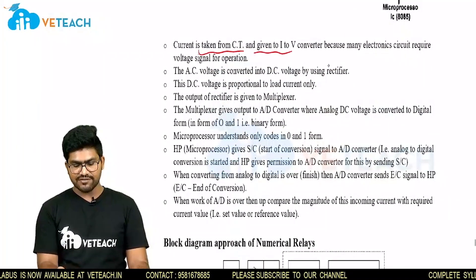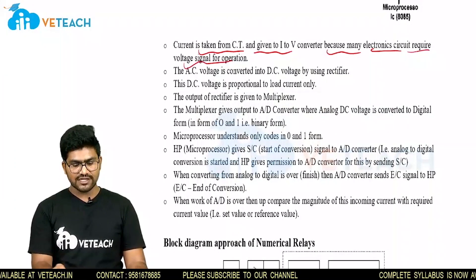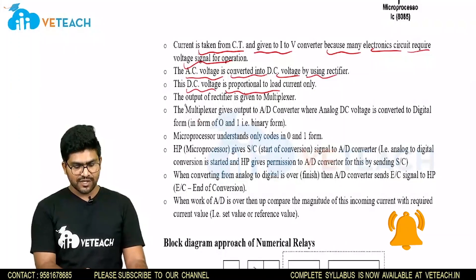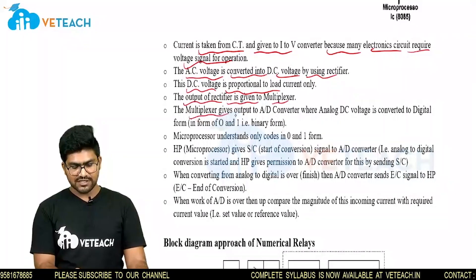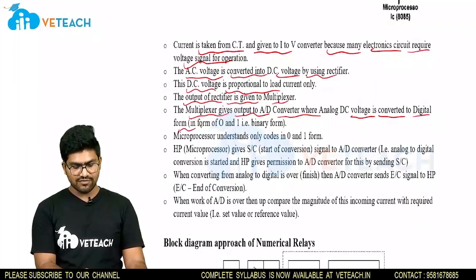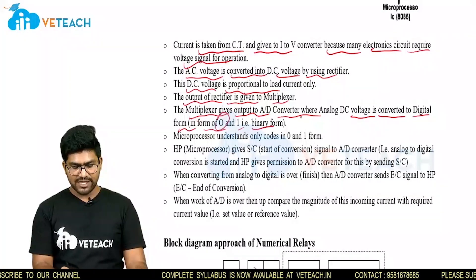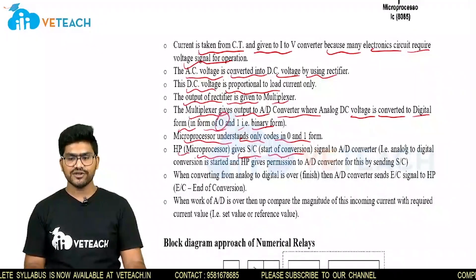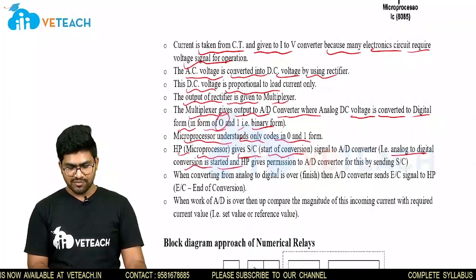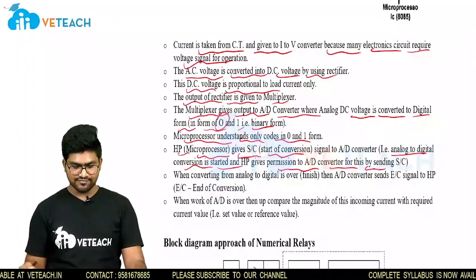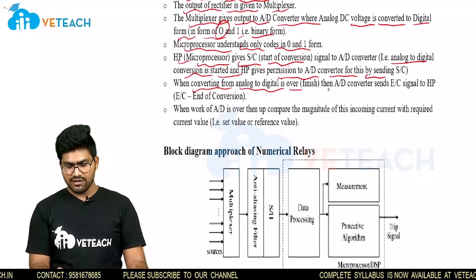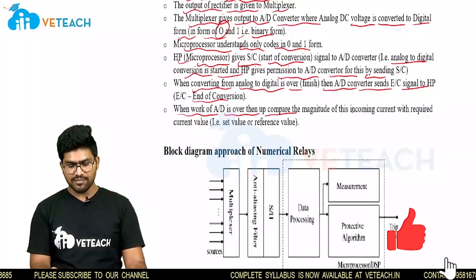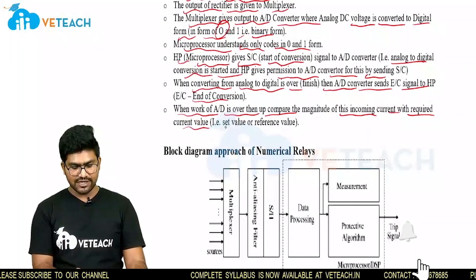Current is taken from the CT and given to the I to V converter because many electronic circuits require voltage signals for operation. The AC voltage is converted into DC voltage by using a rectifier. This DC voltage is proportional to the load current only. The output of the rectifier is given to a multiplexer. The multiplexer gives output to the A to D converter, where analog DC voltage is converted to digital form — that is, binary form of 0 and 1. The microprocessor understands only codes 0 and 1. The microprocessor gives S by C, start of conversion signal, to the A to D converter to begin analog to digital conversion. When conversion is over, the A to D converter sends E by C, end of conversion, signal to the microprocessor. When the work of the ADC is over, the microprocessor compares the magnitude of the incoming current with the required set value or reference value.